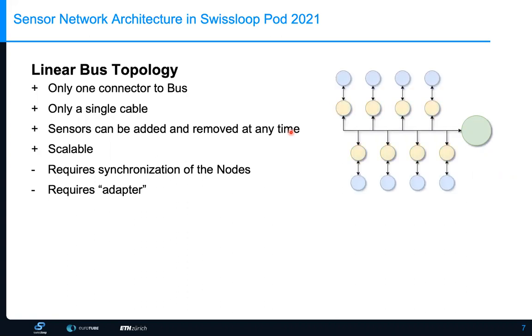Another downside is that you require an adapter for each sensor. In a star topology you can connect every sensor directly, but in a linear bus topology you need an adapter if sensors are not compatible with each other — for example, not every sensor has the same supply voltage or produces the same data format. Some sensors produce an analog signal like current or voltage output, while others have a digital interface. To put everything on the same bus you need a common communication protocol.